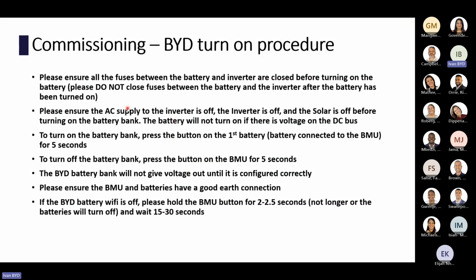That's why we always recommend keeping all the fuses closed between the battery and the inverter before turning the batteries on. It prevents the inrush currents of the caps charging up, and the batteries can test the whole system. When turning the batteries on, please ensure the inverter is off, the solar is off, and the AC supply to the inverter is off. A lot of inverters power the DC bus when the grid or the solar is there, and when you turn the BYD batteries on, they want to test the DC bus before they turn on, and for that they need a dead bus. That's why we ask for that step.